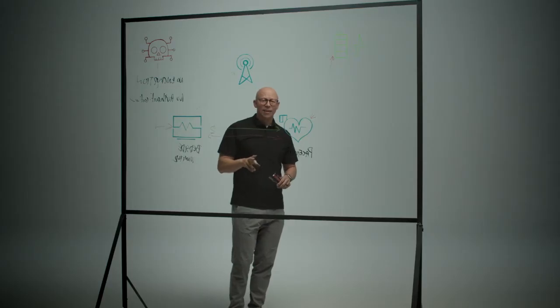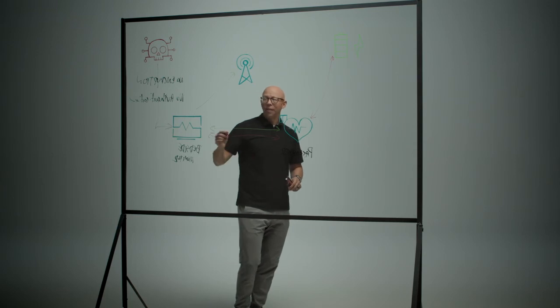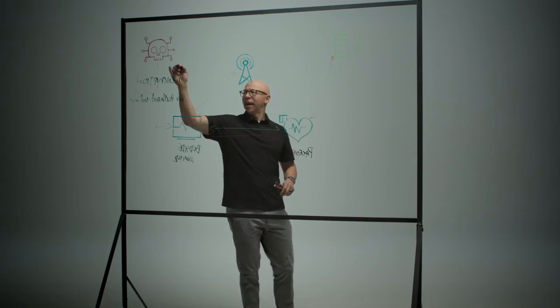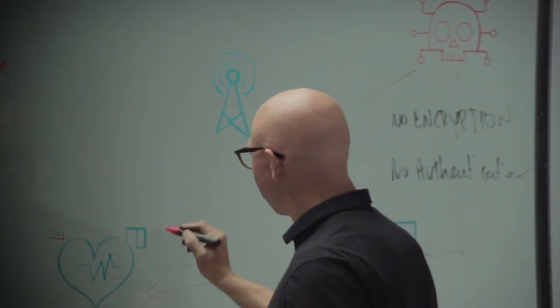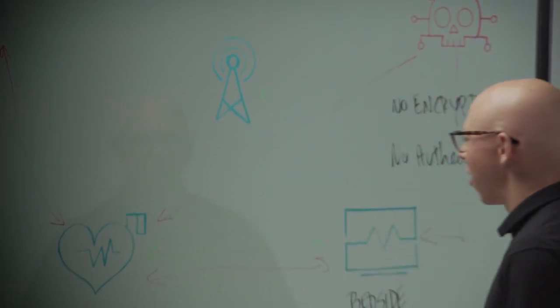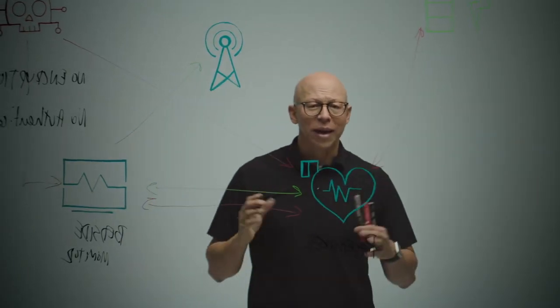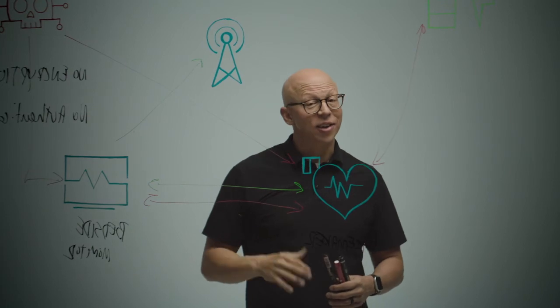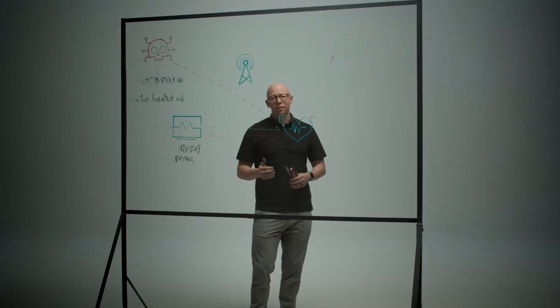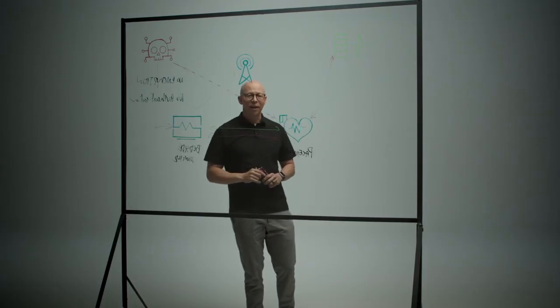The second attack that they performed was known as a crash attack. In this instance, the attackers were able to broadcast repeated messages directly to the cardiac device. Those messages caused the device to malfunction, and in some cases caused the device to pace at very unsafe levels.